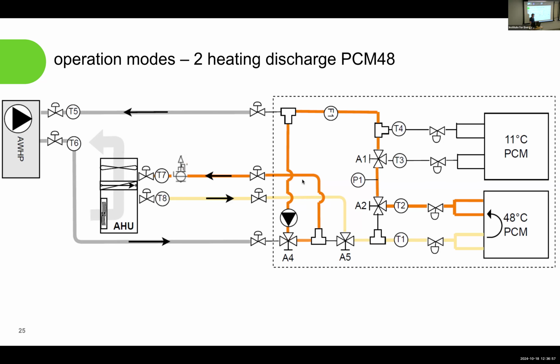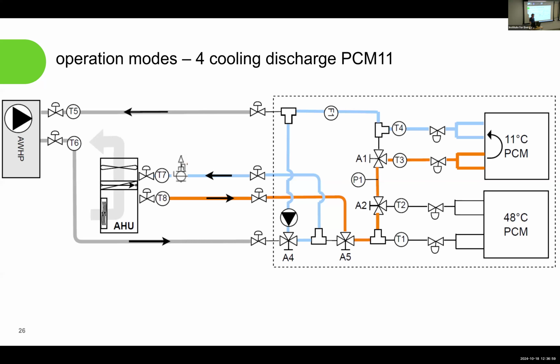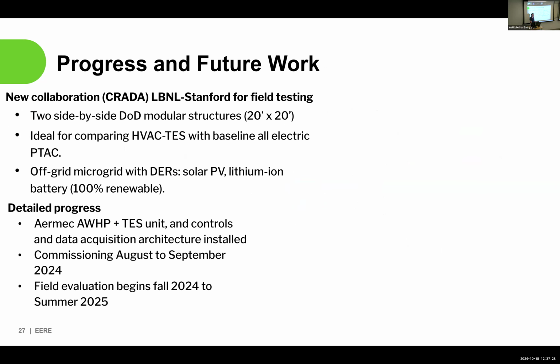So that's utilization of the hot storage. Conversely, if you wanted to use the cold storage, you can imagine relatively warm fluid coming back from the air handler, getting cooled down by the cold storage, and being sent back to the air handler in a loop. During these use modes of operation, you're not using a huge amount of electricity. This pump uses about 40 watts, while the air-to-water heat pump can use up to 4 kilowatts, so that's a significant drop in electricity use during that period.